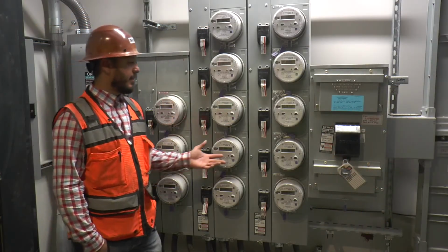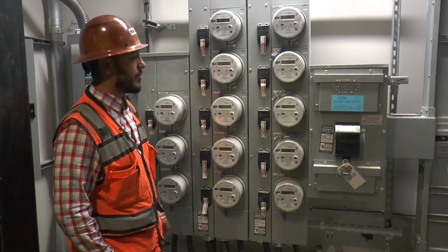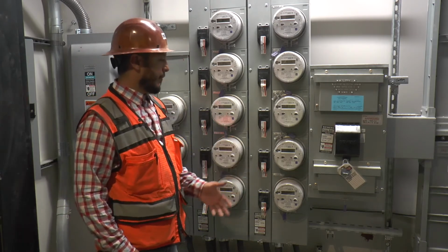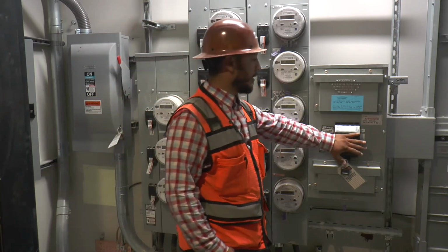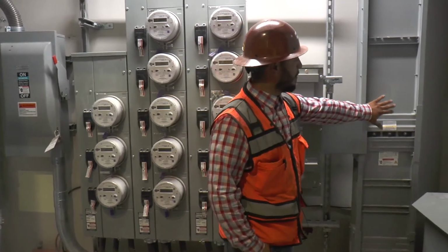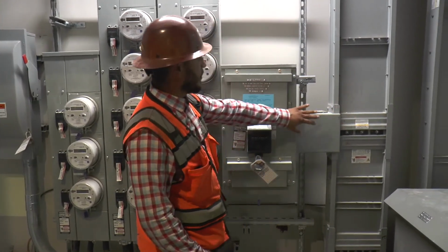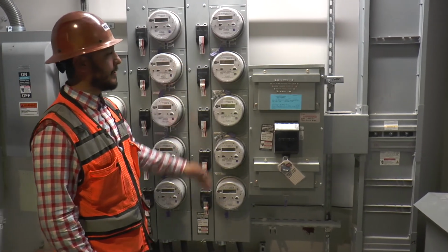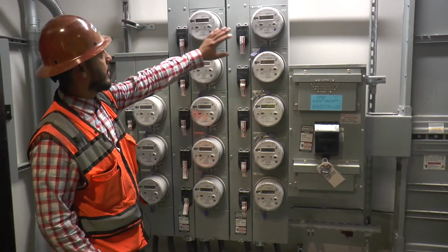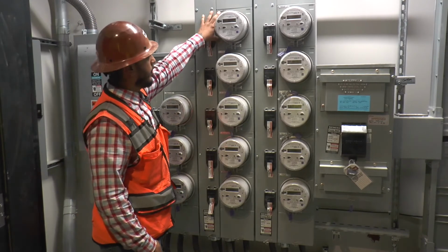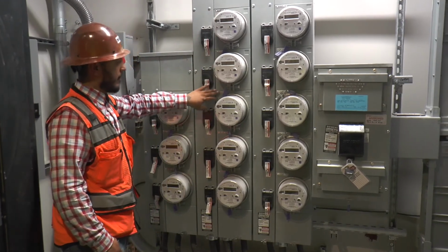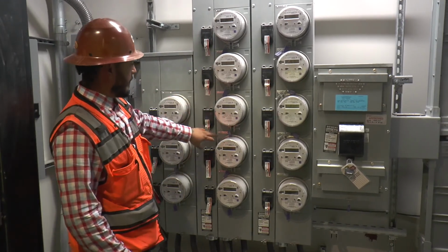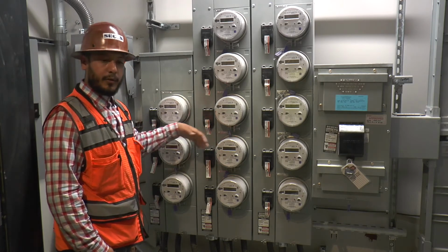All right, this is one of the meter sections off of switchboard 2. This is the first power mod that you'll get off of the bus duct riser, which, this being switchboard 2, feeds from 8 all the way to 18. These are all your meter sockets. Everything's labeled room number per room number. It's identification for APS so they can do their billing.